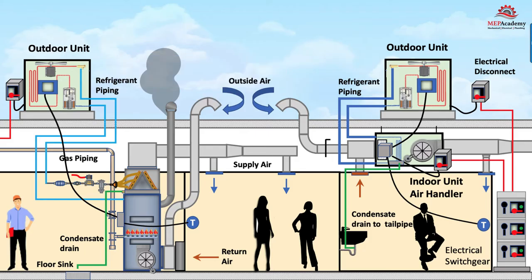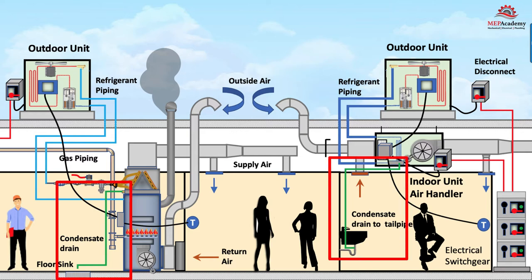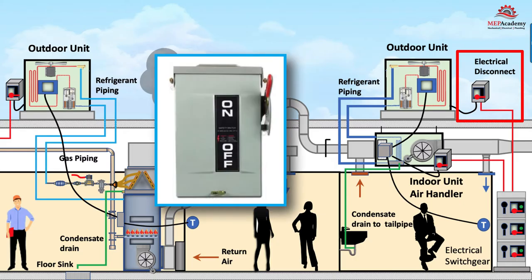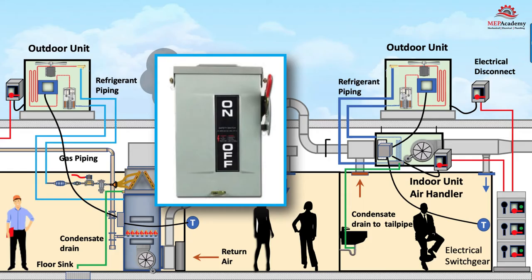You'll need to install a condensate drain pipe from the cooling coil drain pan to an approved receptor like a floor sink or the tailpipe of a sink. Electrical will need to be installed from a breaker panel to a disconnect switch located near the equipment. The disconnect switch is a safety device that allows any technician working on the equipment to lock out the electrical power feeding the HVAC equipment.